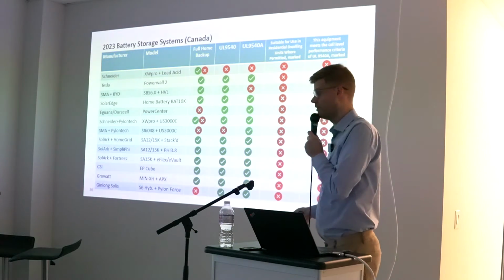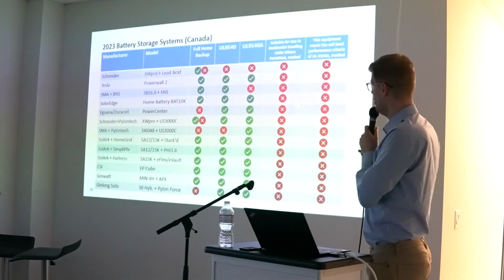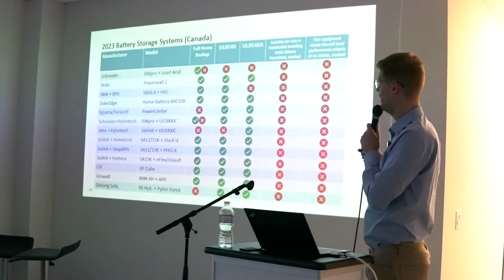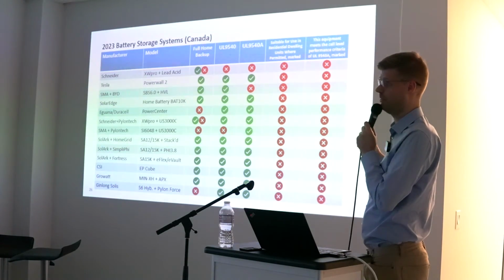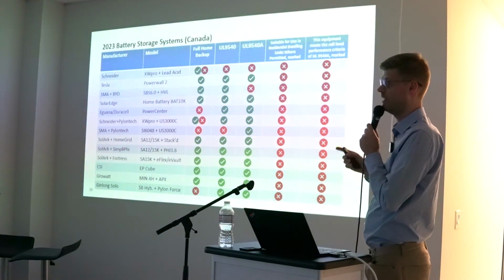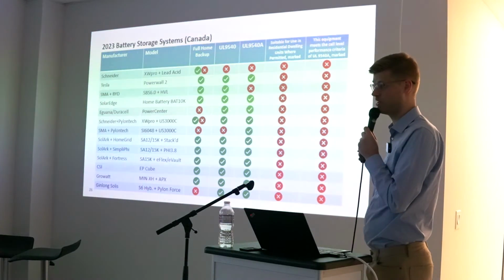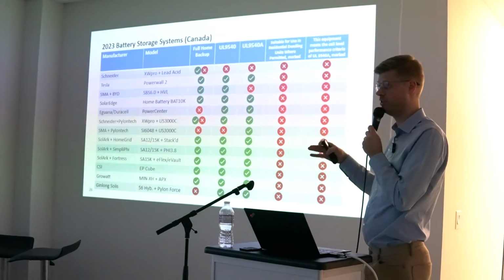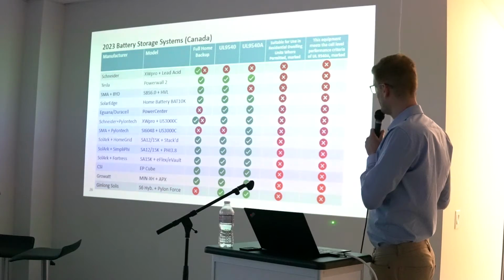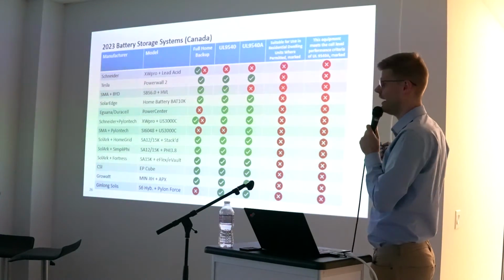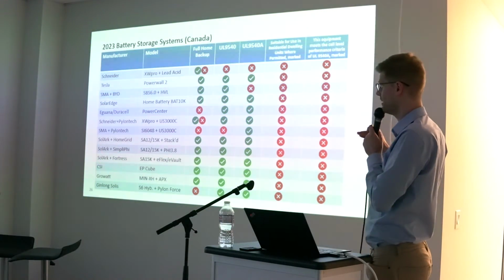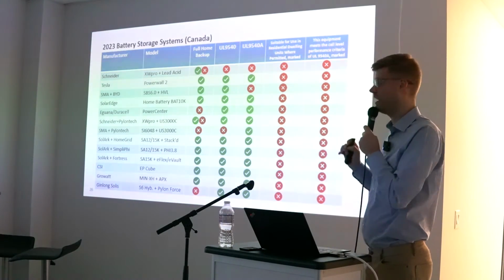And the most important thing you immediately see: none of those systems have a marking on the type label that says suitable in residential dwelling right now. So that's going to change most likely with some iterations of the manufacturer changing their labeling. And none of those manufacturers have passed the criteria for the cell level fire propagation testing.